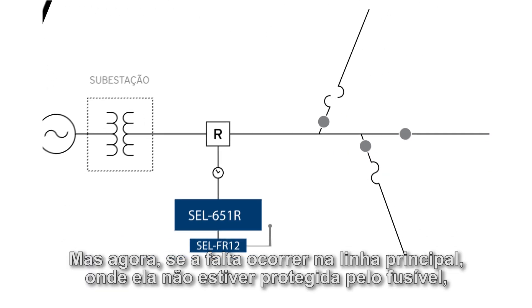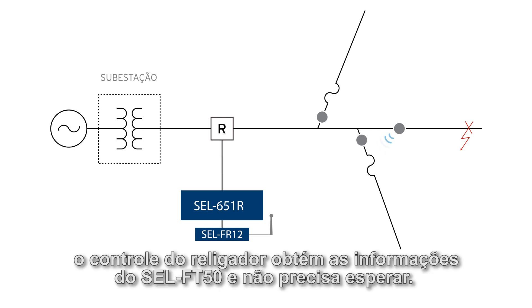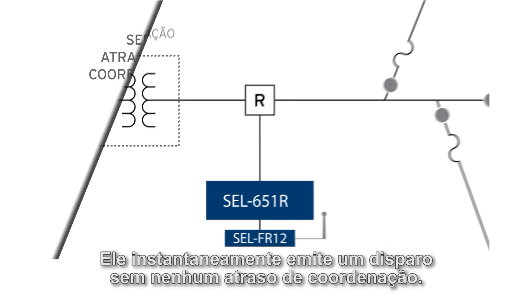But now if the fault happens on the mainline where it's not protected by the fuse, the recloser control gets the information from the FT50 and it doesn't need to wait. It instantaneously trips without any coordination delay.